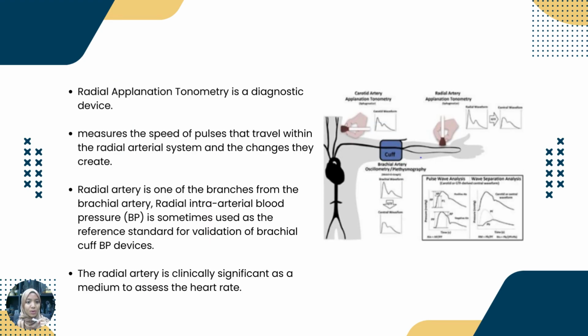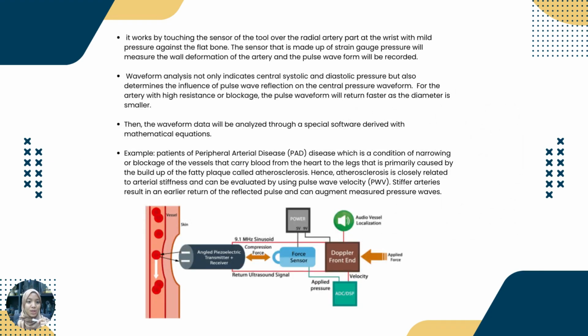For the introduction part, radial applanation tonometry is a diagnostic device that measures the speed of pulses that travel within the radial arterial system and the changes they create. The radial artery is one of the branches from the brachial artery, and it is sometimes referred to as the medium to assess the heart rate. For the working principle, it works by touching the sensor of the tool over the radial artery part of the wrist with mild pressure against the flat bone. The sensor, made up of a strain gauge pressure sensor, will measure the wall deformation of the artery, and the waveform will be recorded. Waveform analysis not only indicates the central systolic and diastolic pressure, but also determines the influence of the pulse wave reflection on the central pressure waveform.